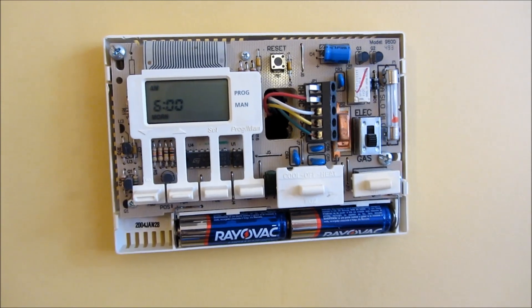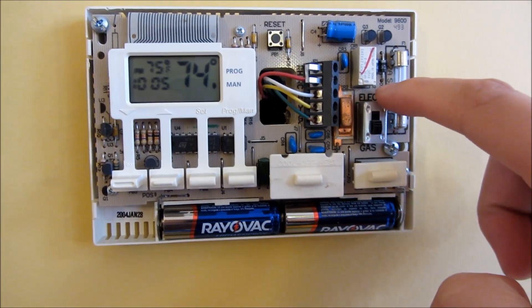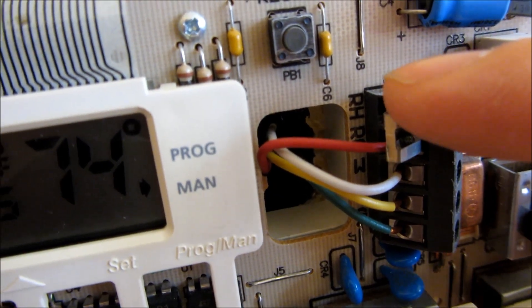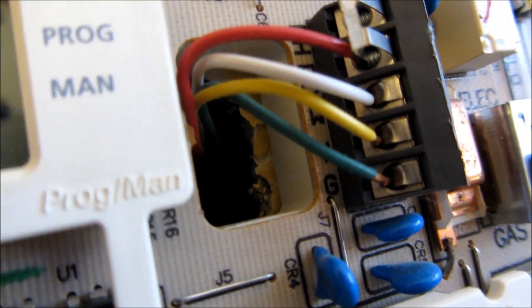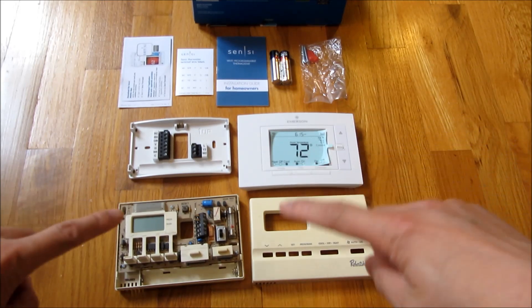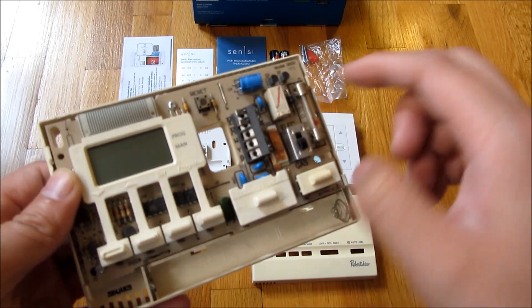Now, the other thing to notice is my old Robertshaw is a model 9600, configured for gas. I'm removing two screws. You want to notice the color coding and order of where the wires are plugged in: RH, RC, W, Y, and green. The wire labels are named more or less by the color of the wire itself. Comparing it to the Sensi, I have the labels RH, RC, W, Y, and G — and there is no C-wire.